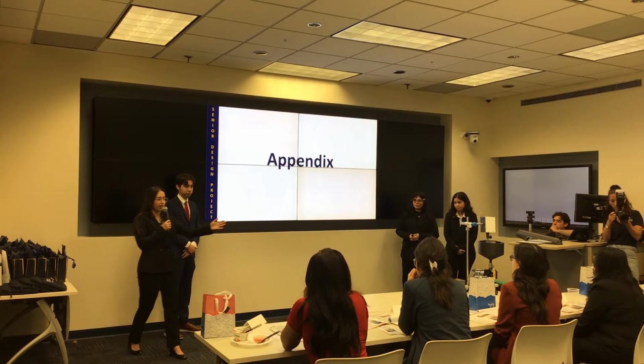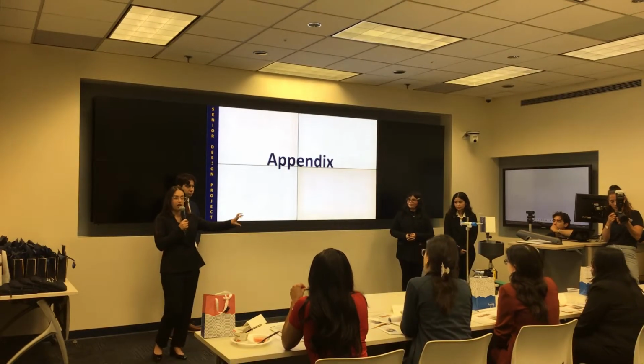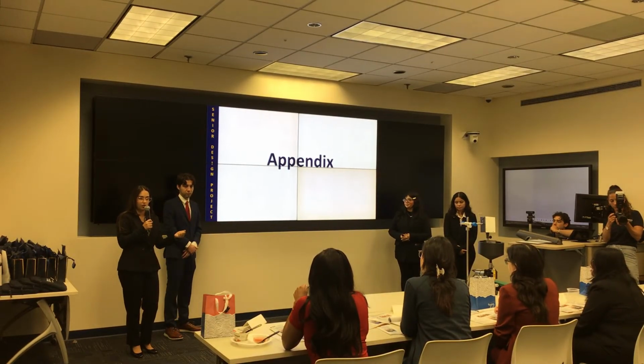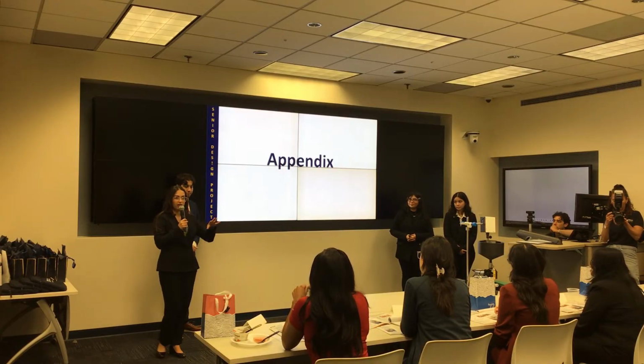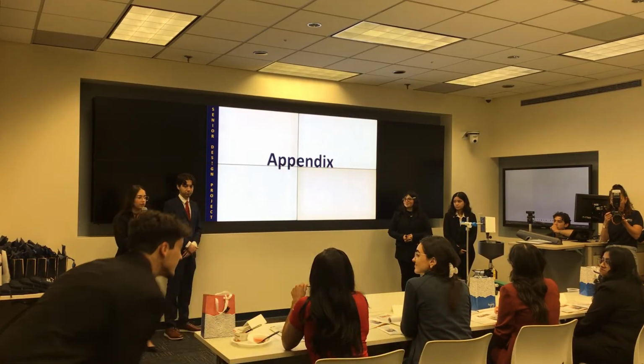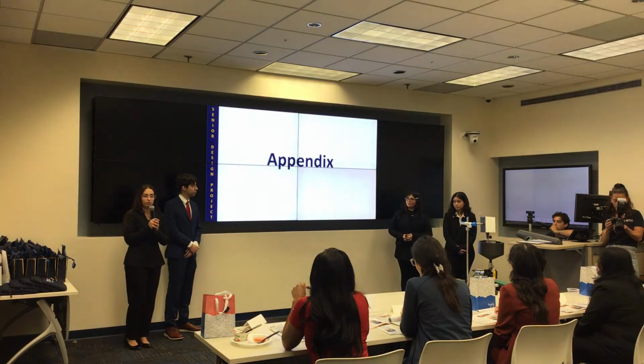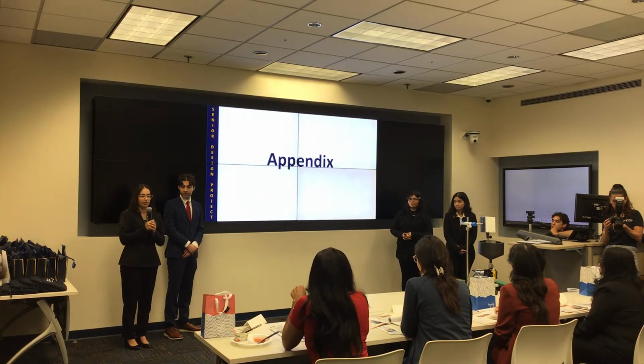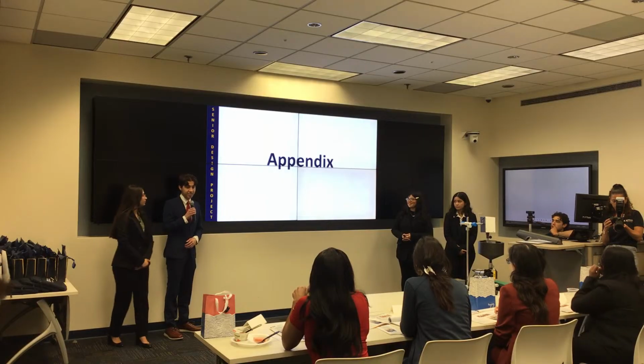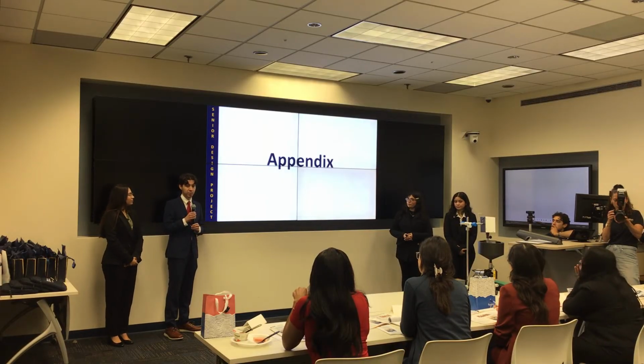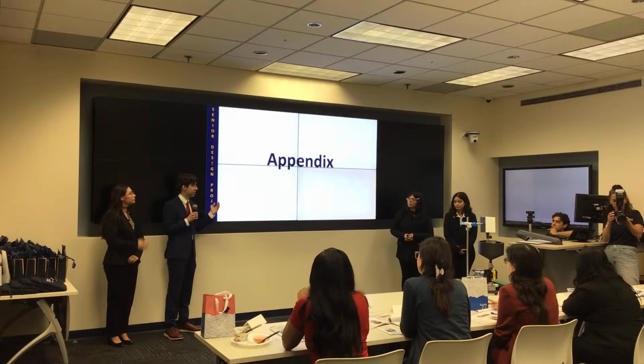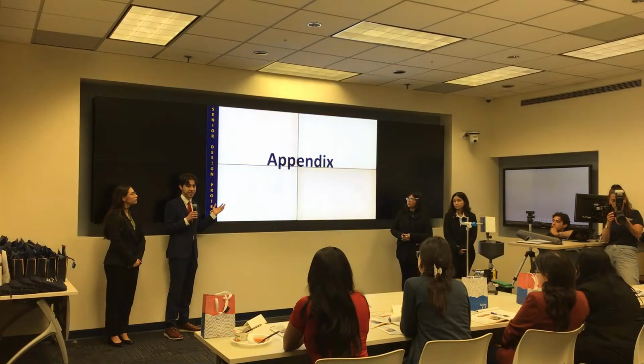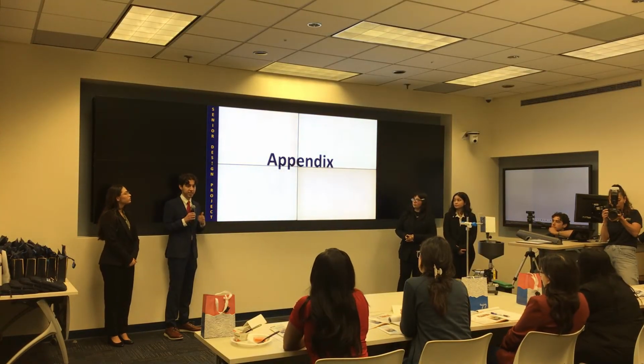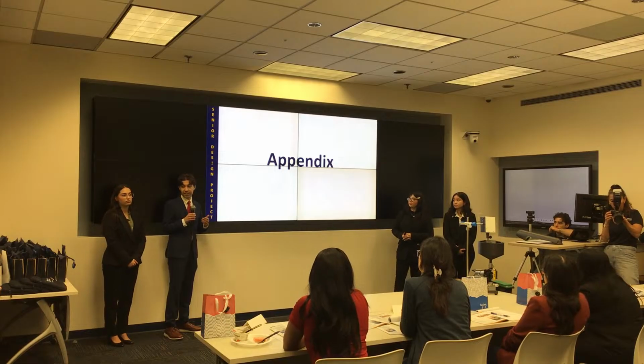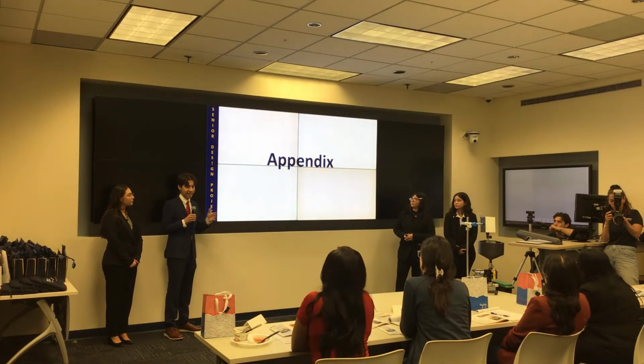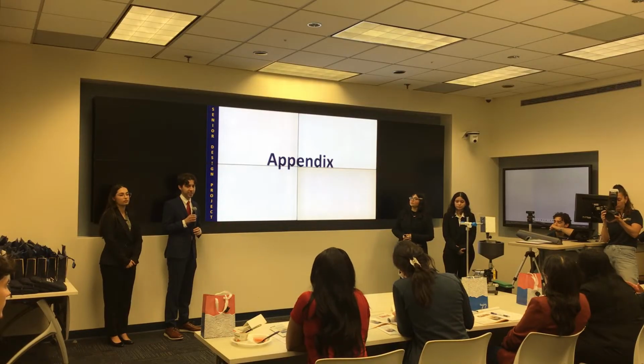In this system, we can reverse the auger, so if it gets clogged, we can pull it back a little bit to control that clogging. If we go back to one of our DIs, we can review the pore size as well. Just a quick follow-up: we did test the pore size using a verification test. That was not brought up for the sake of time in this presentation, but we ensured that our pore size was usable for the expected clumping, and as Natalie mentioned, the variety of viscosities that come with working with stool samples.